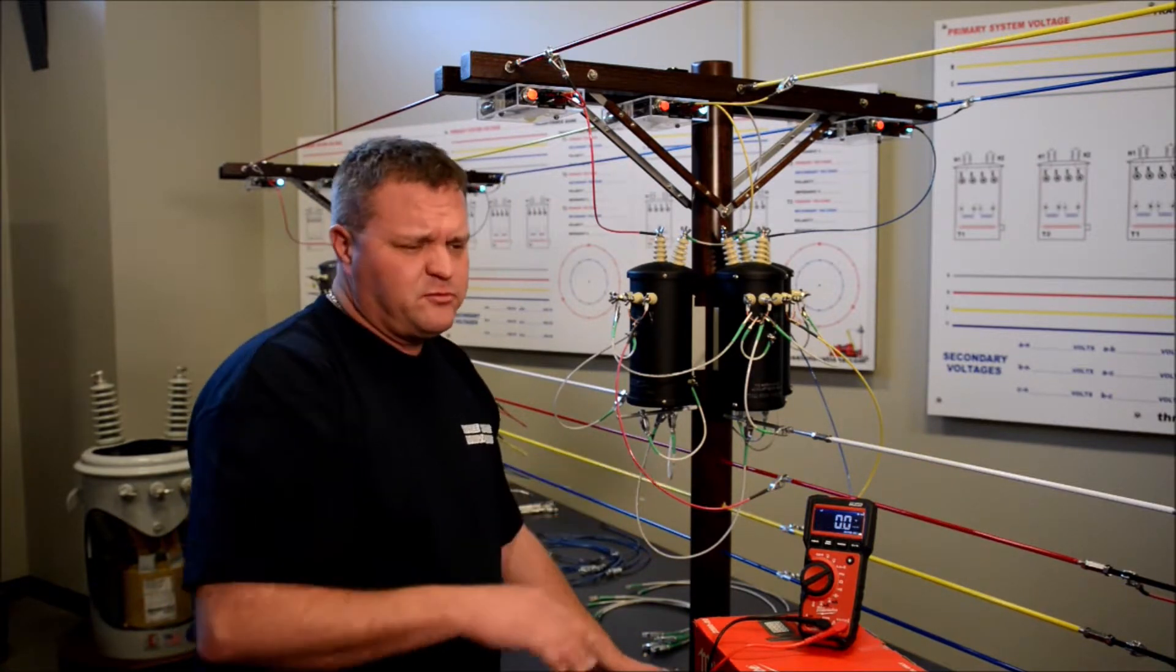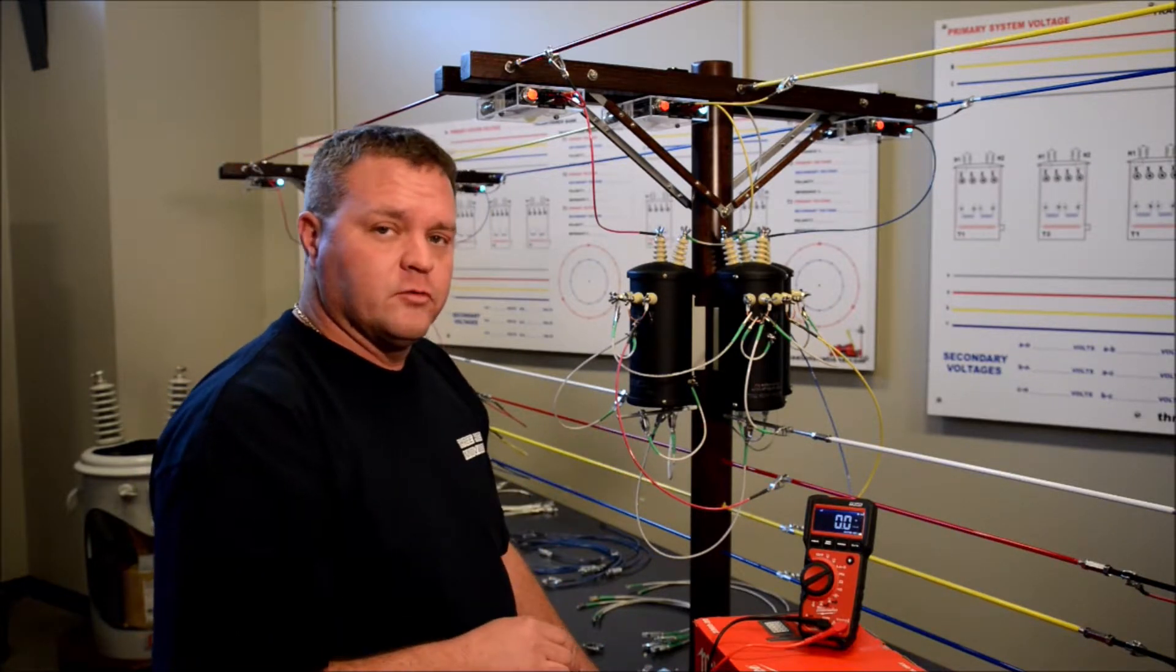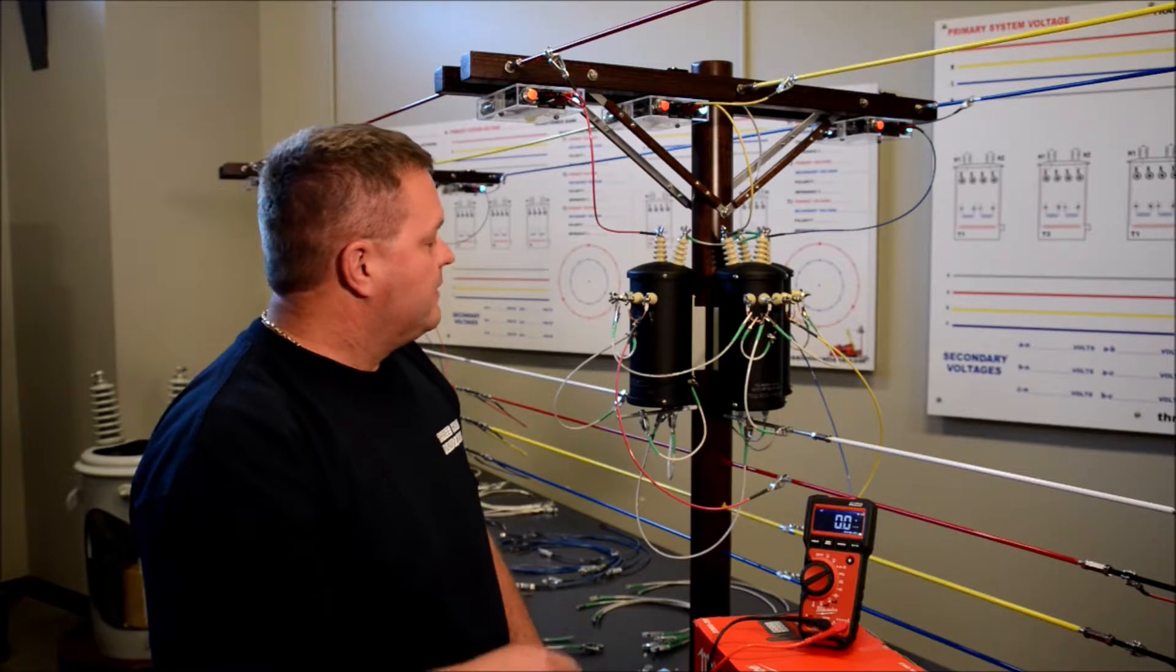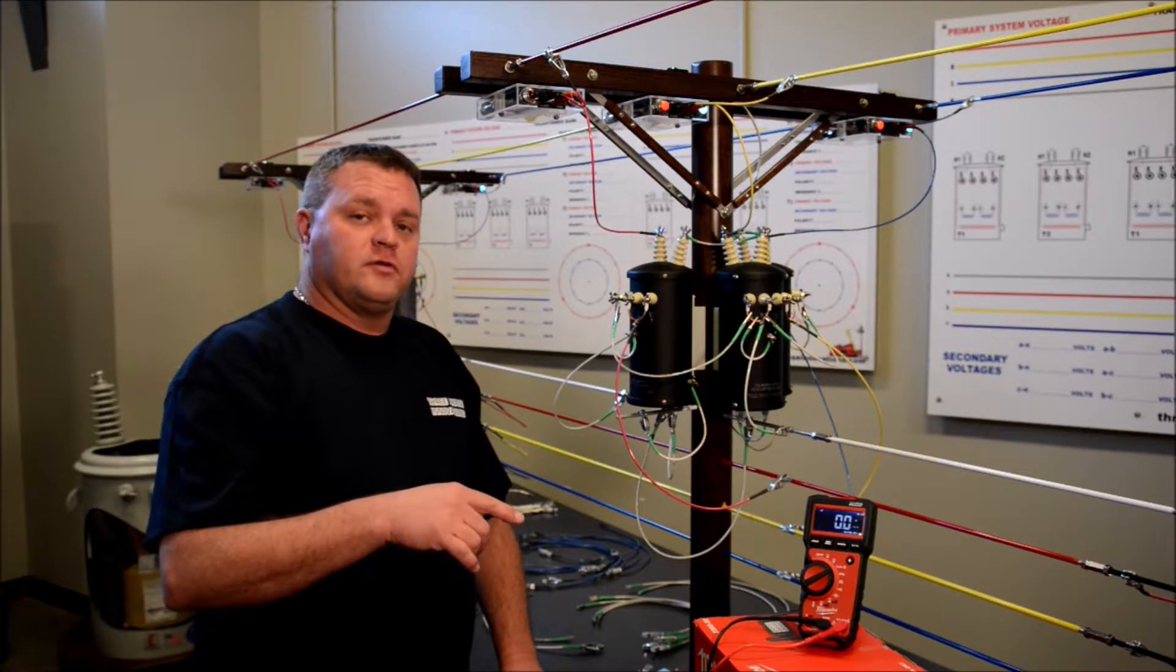Like I said, voltage is a little bit off in the building today. We got a lot of equipment running in this building, but those voltages are acceptable for what we're doing, especially with these little no-load transformers. Now what we're going to do is de-energize the bank and I'm going to float the high side ground.